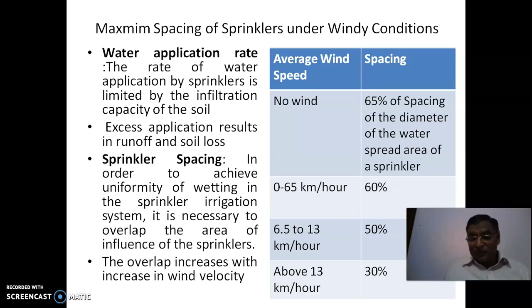So it is necessary to overlap the area of influence of the sprinklers. The overlap increases with the increase of wind velocity. That's what we have seen. Under no wind, it is only 35% overlap. Under less than 6.5 kilometers per hour, it is 40% overlap. Between 6.5 and 13, it is 50% overlap. Above 13 is 70% overlap. This is how it goes on.